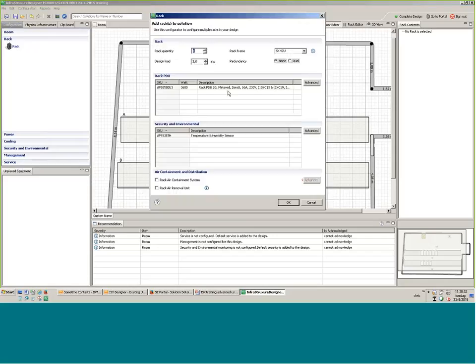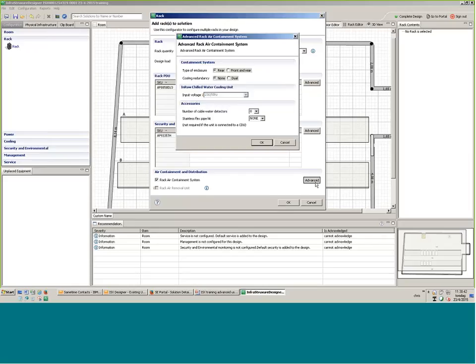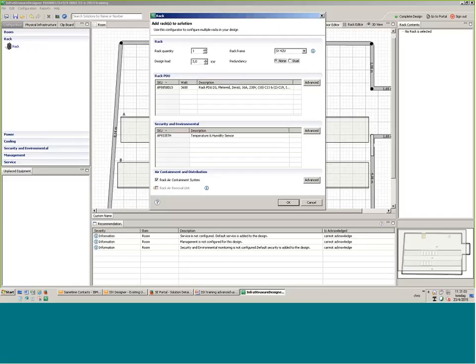Something extra I forgot to mention: down here there's rack air containment system and rack air removal unit. For the rack air containment system, don't use it. They tried to make it better, but it doesn't work. If you want a rack air containment system, just tell my team when you send it in. That's much better, because we have to delete it anyway and make it new. If you have a rack air removal unit, that's the back door, and of course you can add it here.